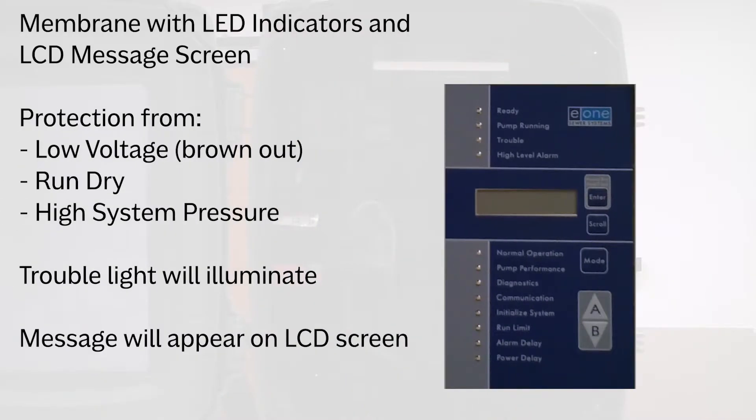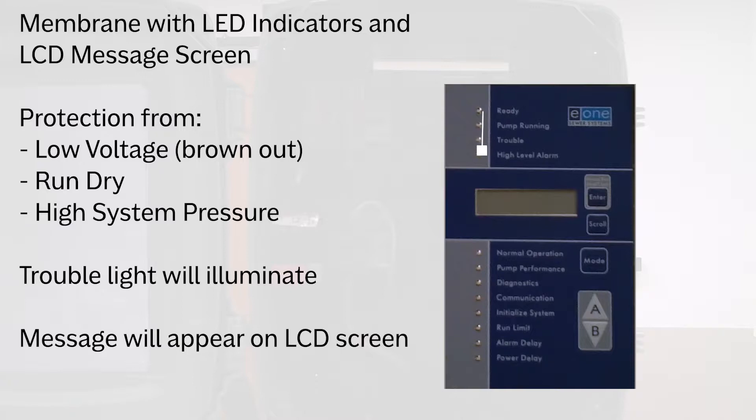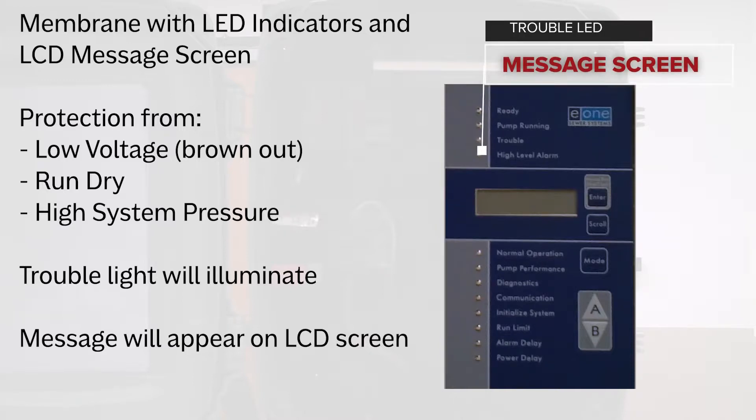The Protect Plus option provides protection from low voltage, so brownout. You'll be able to see a trouble indication and then a message show up on the screen. Run dry and high system pressure will be indicated by a trouble light being lit and then a message showing up on the LCD screen.